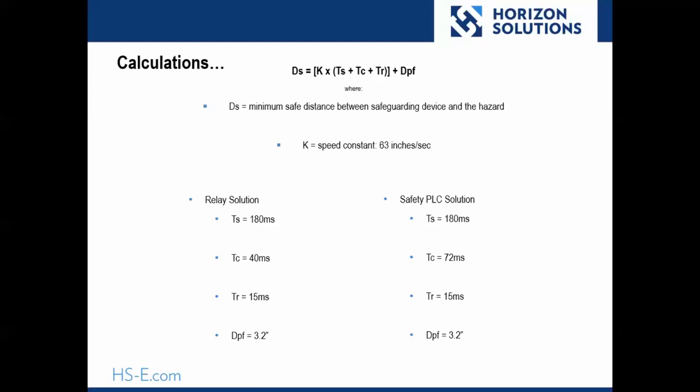Now, using the Rockwell Automation provided GuardLogix reaction time tool, a range of 20 to 72 milliseconds, considering no faults, is found as the reaction time.